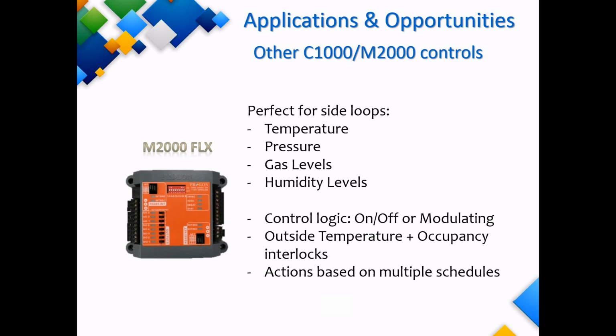Another feature is that the controller can receive multiple schedules, and we can assign each schedule to a different output. This allows us to activate different outputs based on different schedules. People may use this function for lighting control, or perhaps to control multiple exhaust fans based on different schedules.